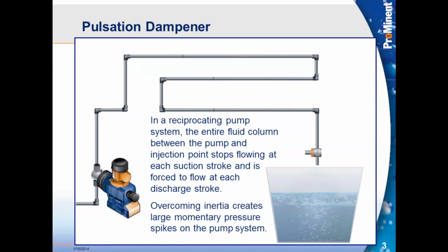We start that in motion. Now we create inertia. That volume becomes a mass in motion, right? It wants to stay in that forward direction. It wants to continue on. Now the pump comes around on the suction stroke, and we're pulling that discharge valve ball down into its seat. We're trying to put it into check. We're trying to stop that forward flow of that volume, that mass that we have moving in the discharge line.